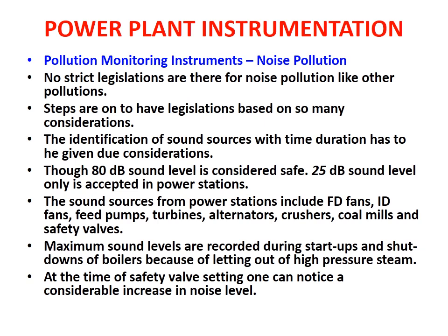Maximum sound levels are recorded during startups and shutdowns of the boiler because of letting out of high pressure steam. So mostly you will find that noise is maximum during the starting and shutting points of the boilers, because the high pressure steam is to be taken outside the boiler, and at the same time a high amount of feed water is to be taken inside the boiler. At the time of safety valve setting, one can notice a considerable increase in noise level when the safety valve is employed in the system. The noise pollution is thus created.